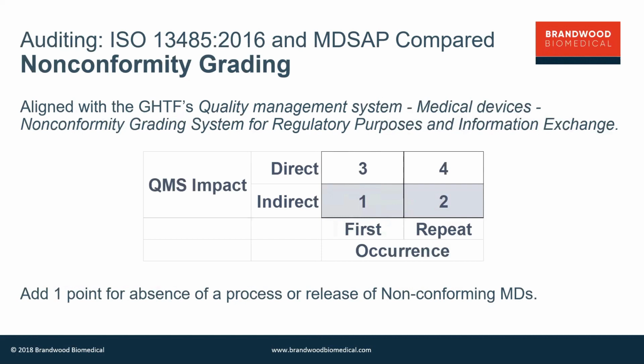So, TJ, can I just interrupt at that point? Yep. And I just want to understand this clearly as well, because what we're talking about is each individual major observation, if you like, gets scored. So it's not a score for the whole audit, it's a score for each thing that comes up that's of significance. Absolutely. And that can be scaled on 1 to 6, and if you hit the 6, that means you've got something that's got a direct impact, it's a repeat occurrence, there's something wrong with the process, and you've also ended up releasing some non-conforming devices. And if you hit all of those bells, then you're not going to pass that particular audit at that time.